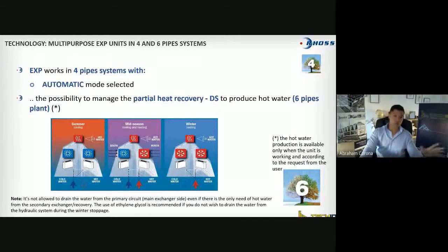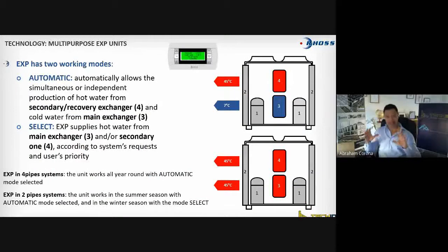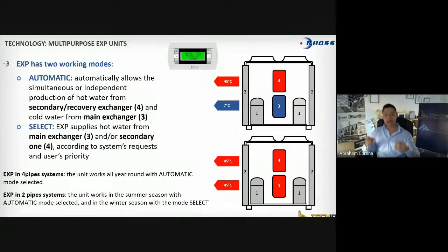So we can do a 4-pipe system and we can do a 6-pipe system with this kind of unit. Actually, we can also do a 2-pipe system. We can cover all the range. These kinds of units out of RHOSS have two modes, the one we call automatic and select, right? Automatic mode is basically we prioritize the production of chilled water. The unit will run most of the time as a chiller. And in select mode, we are prioritizing the use of hot water.